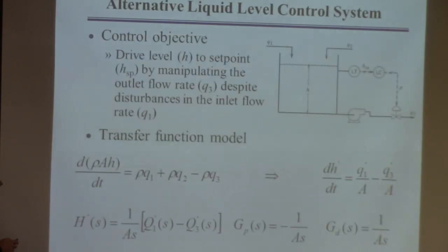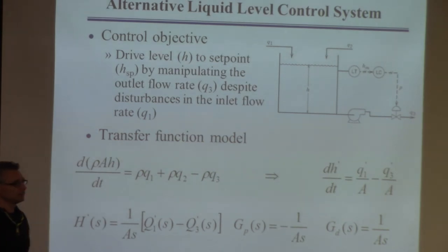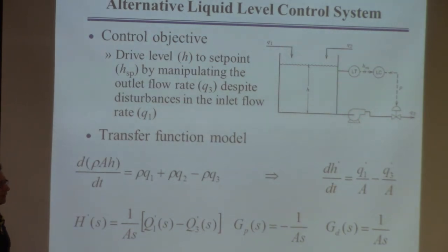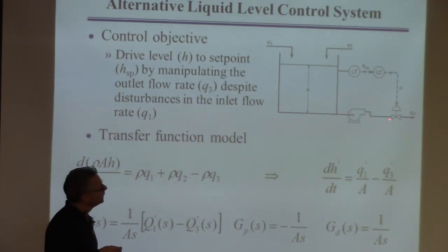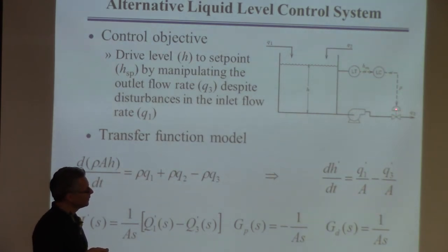Here's a variation on the same system, but now it's the more common way to do level control: two flows in, one flow out, and we control the outlet flow. If you have a pump, you can arbitrarily change the outlet flow — otherwise it would be gravity driven. We measure the level, send that signal to the controller, compare to a set point, and send a signal to the valve.